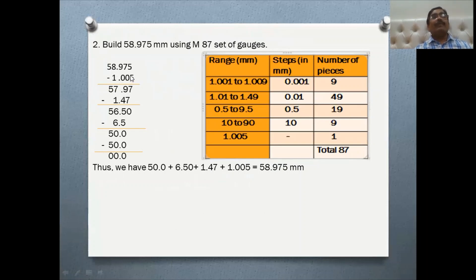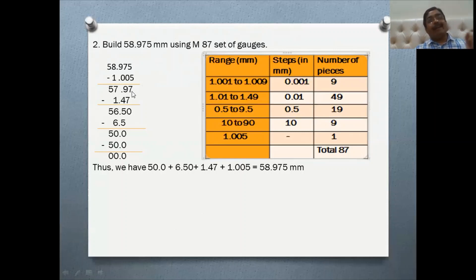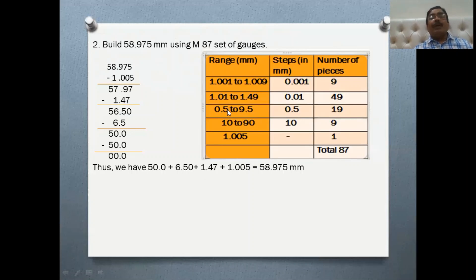Second example: 58.975 mm. Concentrate on the last decimal — 0.005 — so select 1.005; remainder is 57.97. A tip: always use the minimum number of slip gauges. Here 0.97 is considered together — select 1.47; remainder is 56.50. If you get 0.5 as a remainder, select 6.5; remainder is 50. Select 50 from the 10–90 range. Total: four slip gauges build 58.975 mm.